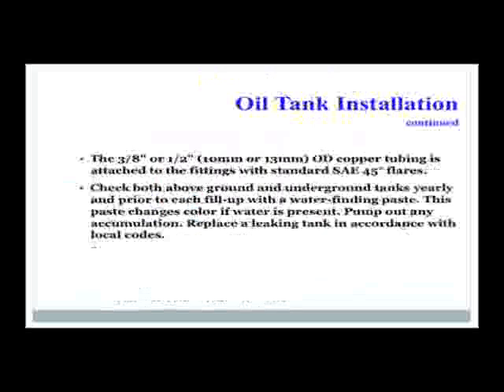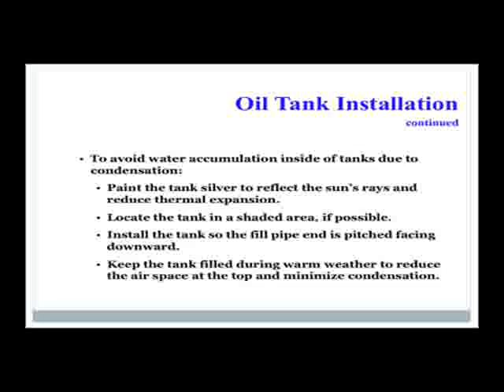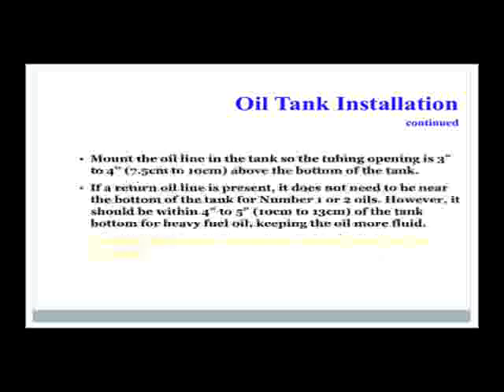Check both above ground and underground tanks yearly and prior to each fill-up with water finding paste. This paste changes color if water is present. Pump out any accumulations. Replace a leaking tank in accordance with local codes. To avoid water accumulation inside tanks due to condensation, paint the tank silver to reflect sun's rays and reduce thermal expansion. Locate the tank in a shady area if possible. Install the tank so the fill pipe end is pitched facing downward. Keep the tank filled during warm weather to reduce airspace at the top and minimize condensation.